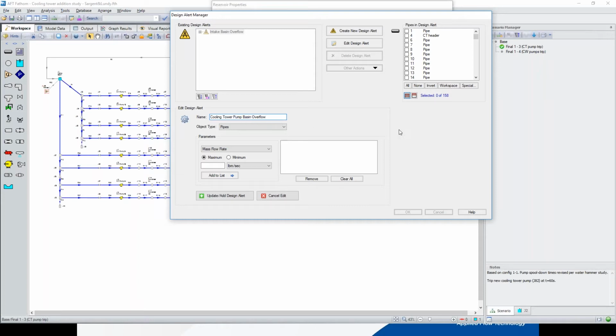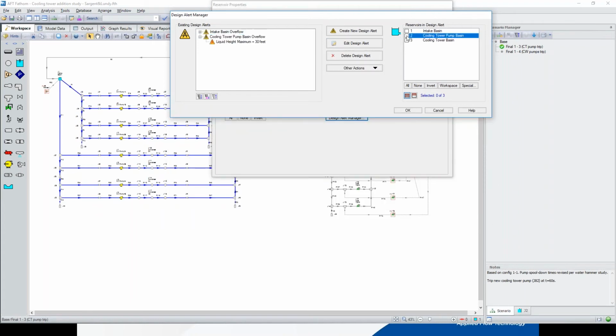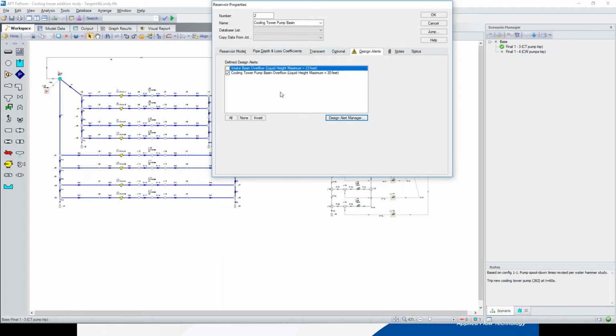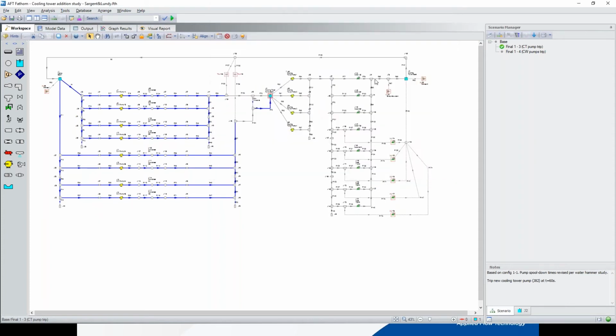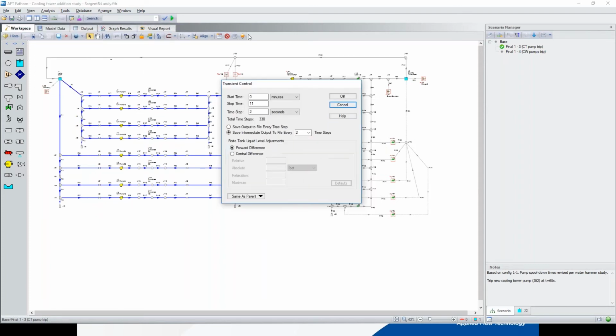So I go to design alert manager. I say create a new one. We're going to give it a name, and we're going to call it cooling tower pump basin overflow. The design is for the reservoir liquid height, a maximum of 30 feet. We add it to the list. We update, and we come here and we're going to apply this design alert to the cooling tower basin. So we say okay. Now we have a design alert activated for the cooling tower, and anytime there's overflow in the cooling tower, we will receive a warning telling us that there's an undesired condition in the process.